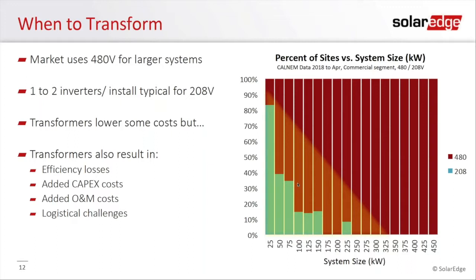So you do have to pay for that transformer. You do have to pay for wiring that system up. You might end up pouring concrete pads, doing other infrastructural changes, and that comes into the CapEx. There's operation and maintenance costs. So now you've got another large electrical component in the system. In a lot of cases, it's a single point of failure type of setup, where if that system goes down, you need to be there very quickly to repair it.